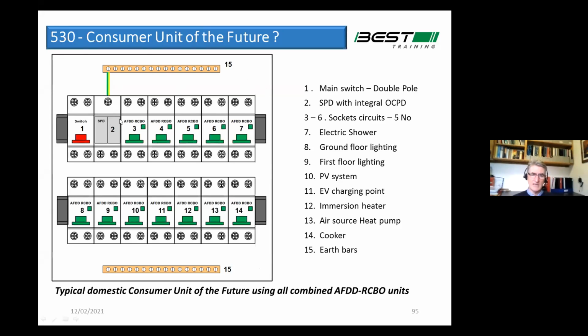So we've the surge protection device, and then we simply have whatever it is there, about 11 combined RCBO AFDDs. And it's very simple then. Each circuit just comes in, it individually terminates onto its own pair of terminals, and you just bring up your earth wires onto the earth bars here. It's very simple, nothing complex about it. That's one approach to it.